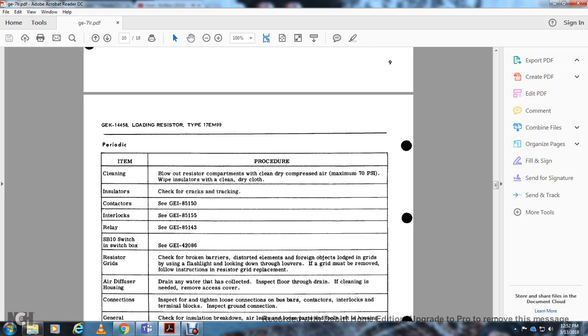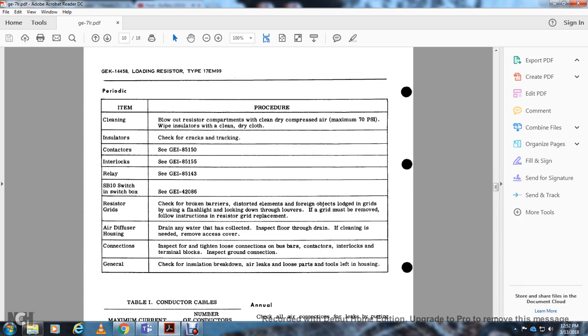85 150. Interlocking. GEI-85155. Relay. GEI-85143. SB10 switch in switch box. GEI-42086. Resistor grids. Check for broken barriers, distorted elements, and foreign objects lodged in the grids by using a flashlight looking down through the louvers.